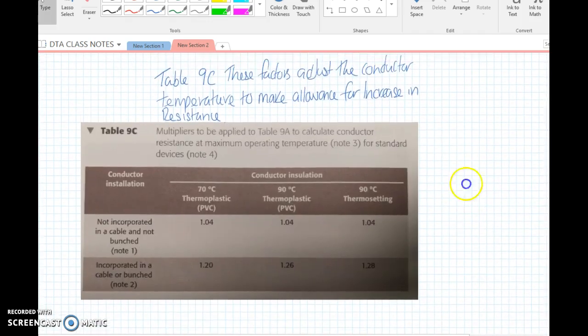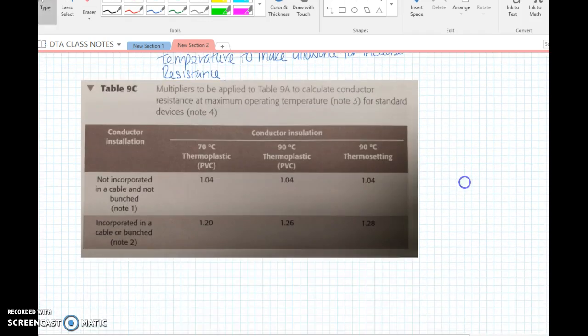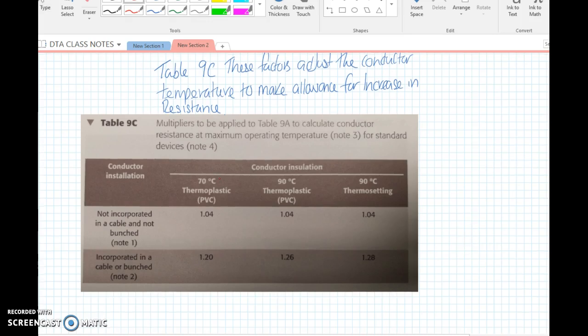The final adjustment factor table: normally our installation cables at 20 degrees will have a certain resistance, for example a 2.5mm R1, 1.5 R2 will have a resistance of 19.51 milliohms per meter at 20 degrees. But that PVC cable can operate up to 70 degrees, which affects its conductor resistance. As electric current flows through the cable, that will cause the resistance to increase.